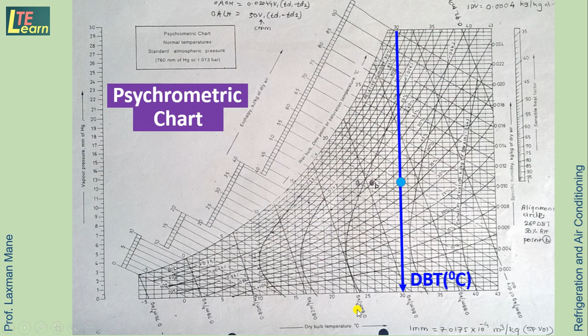Here is a horizontal line passing through this point. On the right side is a scale of specific humidity where we find the value of W in kg per kg of dry air. On the left side, on the saturation curve where this line will reach, the dew point temperature is obtained. This is a line which gives wet bulb temperature. Extension of this line on the enthalpy scale gives the value of H in kilojoule per kg. This is a curved line which represents relative humidity in percentage.